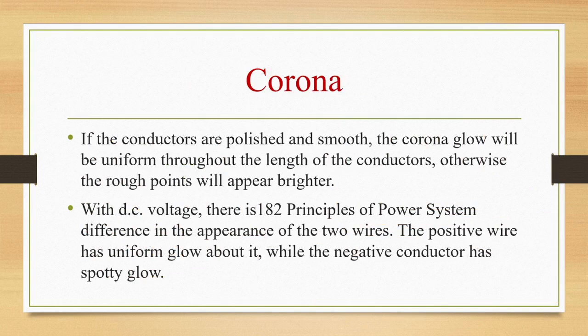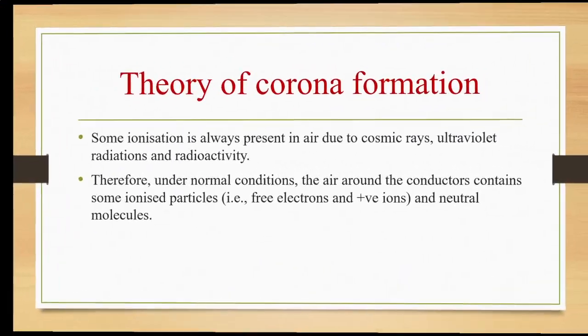If the conductors are polished and smooth, the corona glow will be uniform throughout the length of the conductors. Otherwise, rough points will appear brighter. With DC voltage, there is a difference in the appearance of the two wires. The positive wire has a uniform glow about it, while the negative conductor will have a spotty glow.